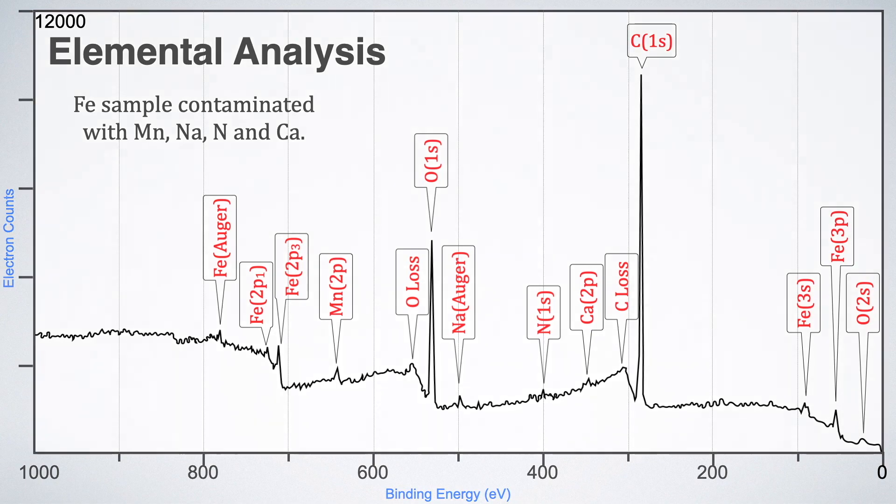Also, some small peaks at 781 electron volt and 498 electron volt represents Auger peaks. Auger lines are appearing because of energy transfer from one electron to the other electrons during photoemission process. This also we will discuss in detail in next videos. For now, we can easily find the number of elements present in our sample just by matching the binding energy of different peaks with the standard values as given in the table.